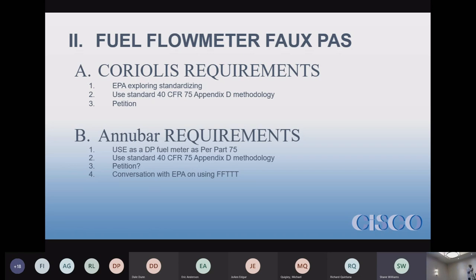The Annubar issue. One of the things is that the Annubar, from my understanding and from talking with the EPA scientists, has a lot of similarity with the orifice plate in how it operates. And so this particular facility was basically doing the same type of calibrations that you do for an orifice plate. An orifice plate allows you to do something that other meters don't. That orifice, nozzle, and venturi allow you to do what? You're nodding, so I know you're an agreeable guy. Does anyone know?